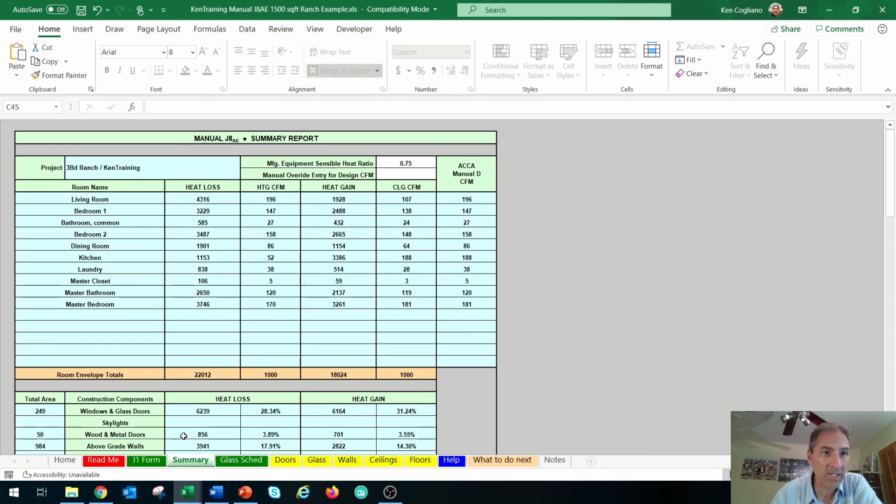When you go to your summary tab, the program is going to give you heating CFM and cooling CFM. If you look at my channel, you'll see I don't exactly trust these numbers. I have a complete video on why I don't trust these numbers, because heating CFM should be less than cooling CFM.